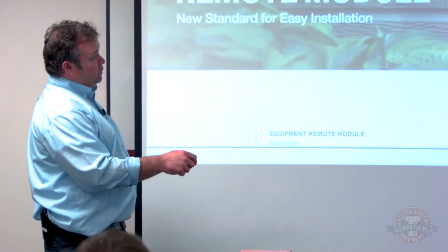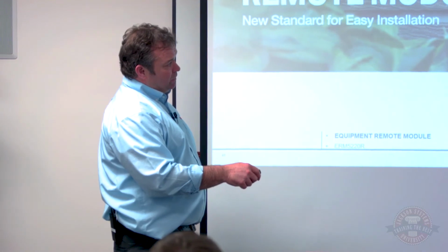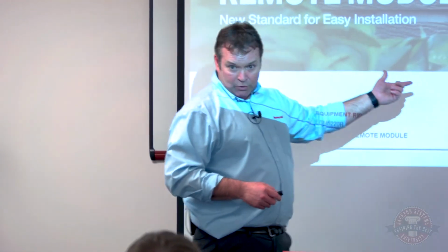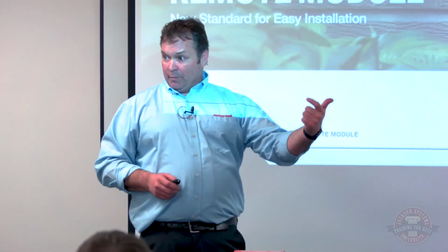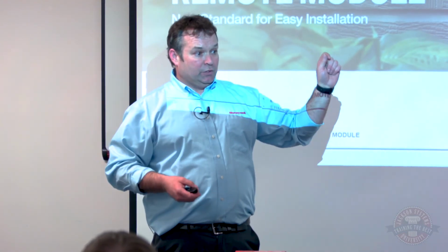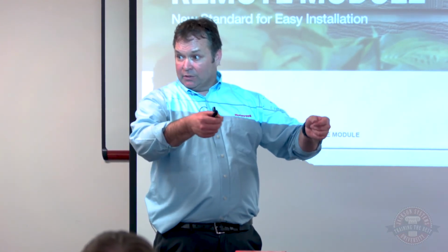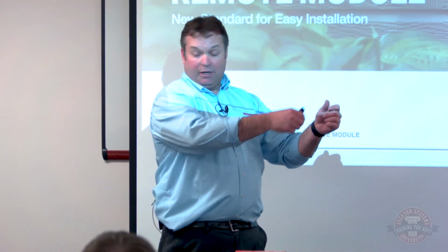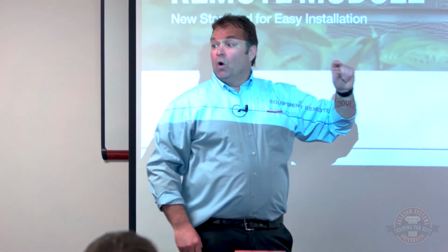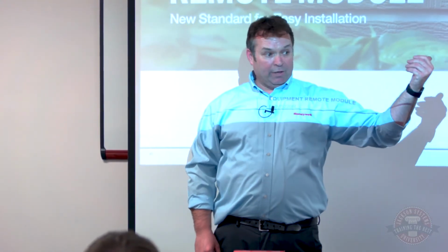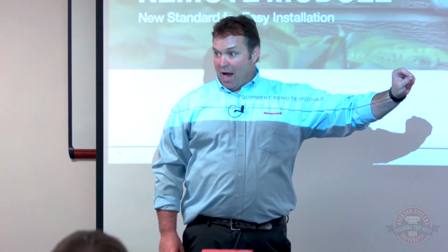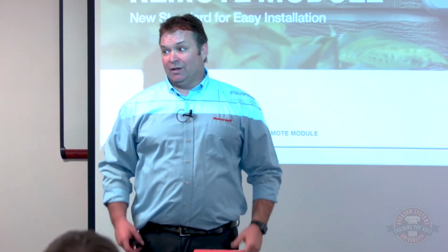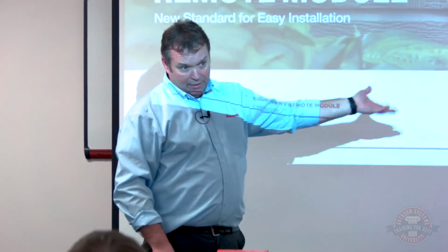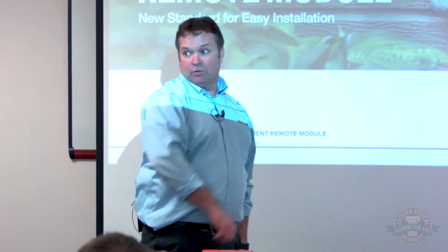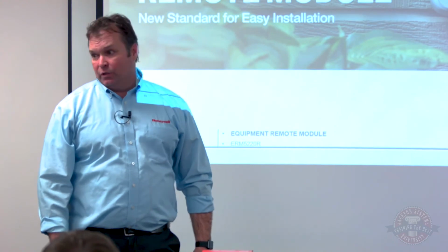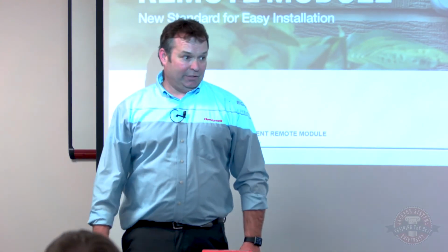So we wanted you to mount it on the outside of the house, and you have to have 24 volts to it. So if you got a good 2-wire coming out there and you're upgrading to a heat pump, just take it off the common and yellow that's on the furnace, hook it to RNC, and power it. Or I could put a little transformer in there and take one leg of my contactor and power it, and then I'll have power to it. I just got to have 24 volt. And then you wire that into the condenser. It wirelessly sends you all the Y1, Y2, switch over valve and everything, okay?